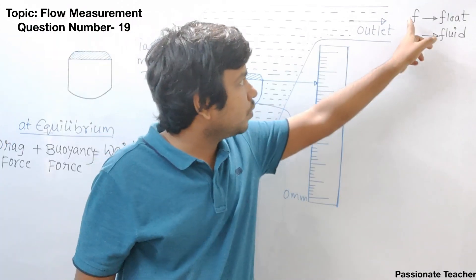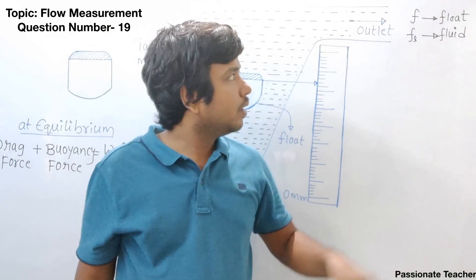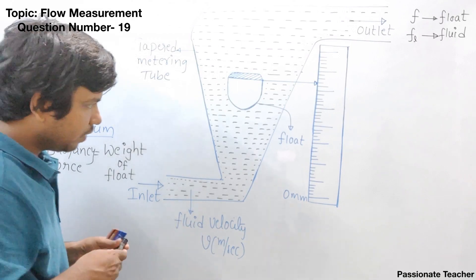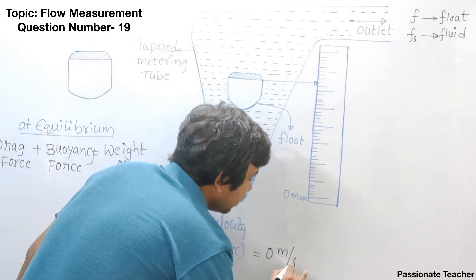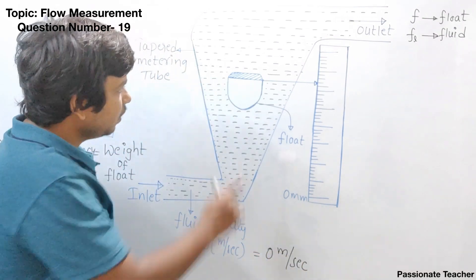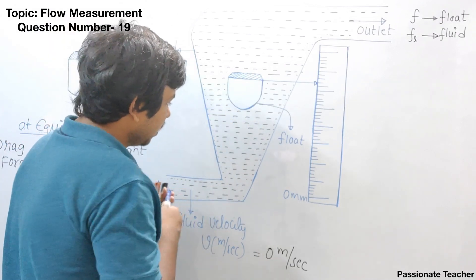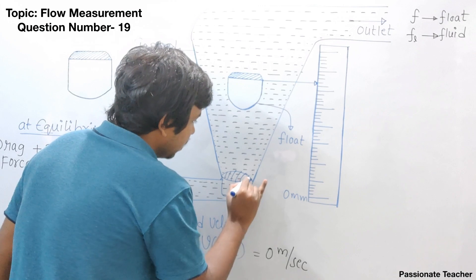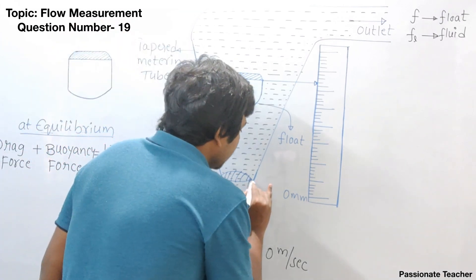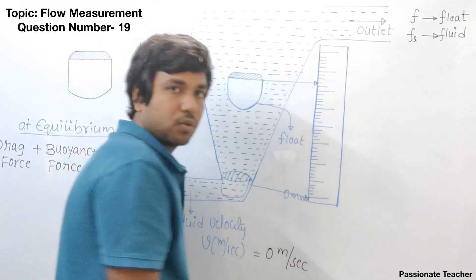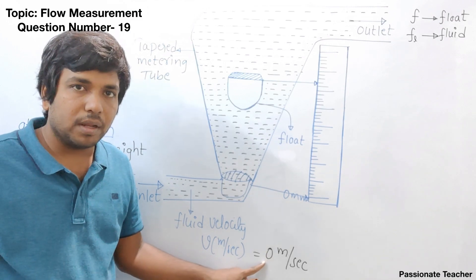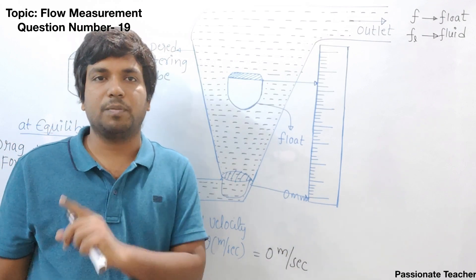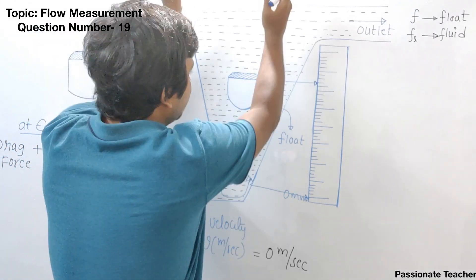Throughout this explanation, if I use 'F' alone it means float; 'f sub s' means fluid. If the fluid average velocity is equal to zero meters per second, the fluid is static. When the fluid is static, the float will rest at the bottom, indicating exactly zero on the scale. This is why the rotometer is called an indicating type instrument. Also, the rotometer is always placed vertically so that the gravity component is present.